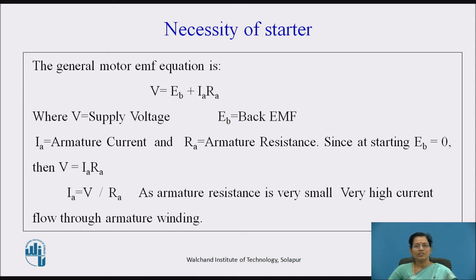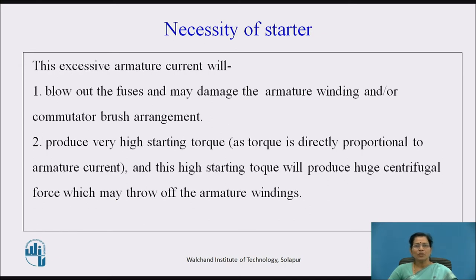As the armature resistance is very small, very high current flows through the armature winding, and due to that, the armature winding may burn. To limit the starting current through the armature winding, we use starters — that means a resistance is inserted in series with the armature winding. This excessive armature current will blow out the fuses and may damage the armature winding or commutator brush arrangement.